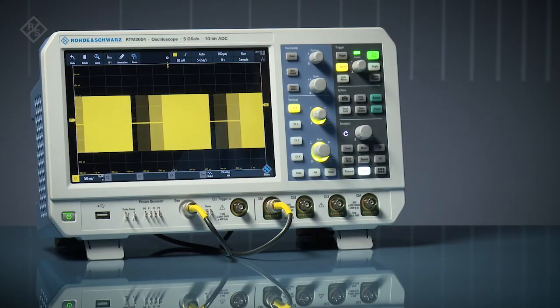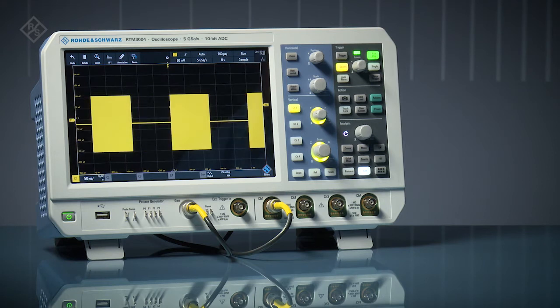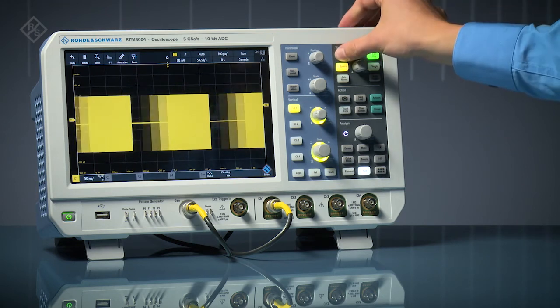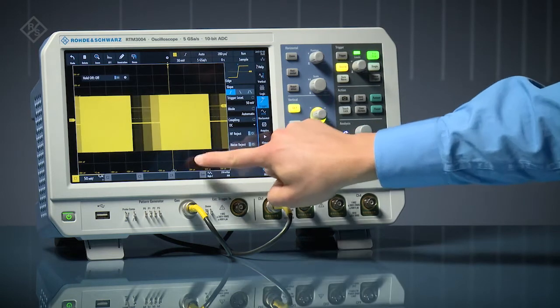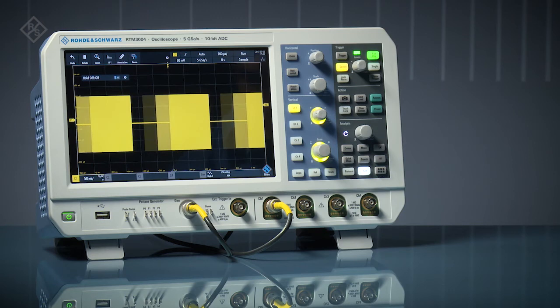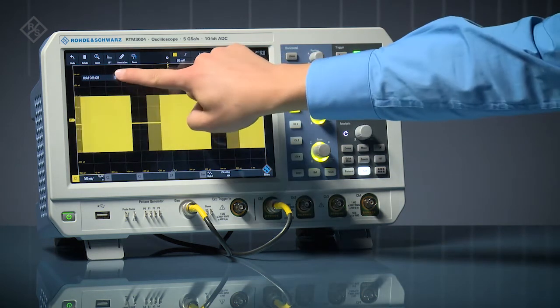Rohde & Schwarz RTM 3000 Series Oscilloscopes feature quick access. To get a stable trigger on this bursted signal, we use trigger holdoff. Quick access lets you drag any menu item, in this example trigger holdoff, directly on the main display. Use the quick access field to enable it.